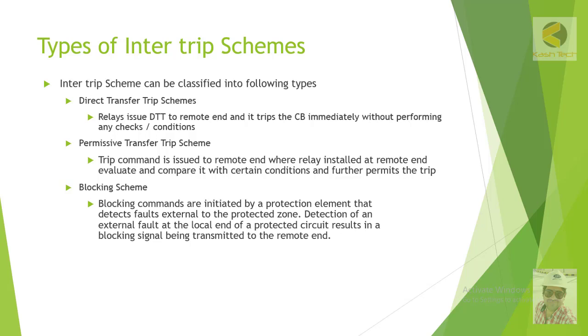In the Permissive scheme, a relay is waiting for a permissive command from the remote end. Whereas in the Blocking scheme, the relay is always ready to trip unless it receives a blocking signal from the remote end. By applying reverse command logic, it could also become an Unblocking scheme, which is another type that we will discuss in detail.